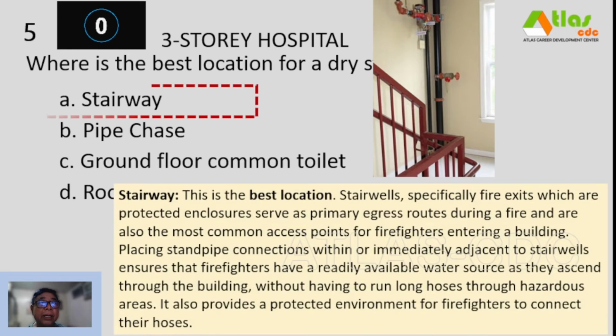And our correct answer is letter A, stairway. So usually, no, dry standpipes located sa floor landing ng mga stairways or in fire exit staircases. So this is the best location. Stairwells, specifically fire exits, which are protected enclosures, serve as primary egress routes during a fire and are also the most common access points for firefighters entering a building. Placing standpipe connections within or immediately adjacent to stairwells ensures that firefighters have a readily available water source as they ascend through the building without having to run long hoses through hazardous areas. It also provides a protected environment for firefighters to connect their hoses.